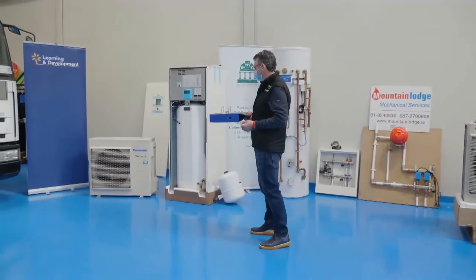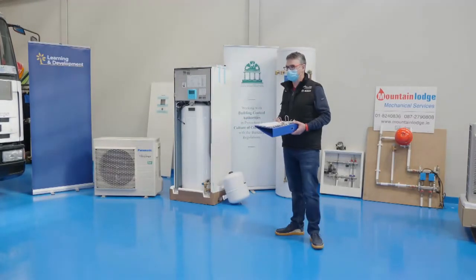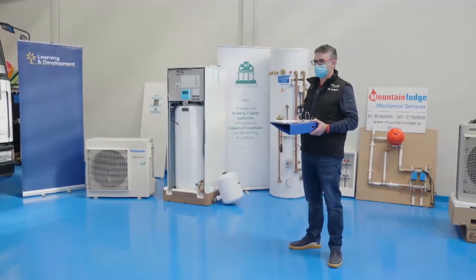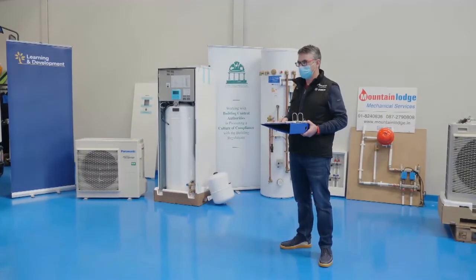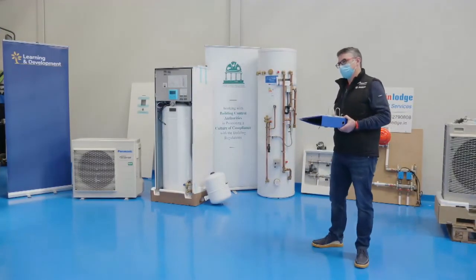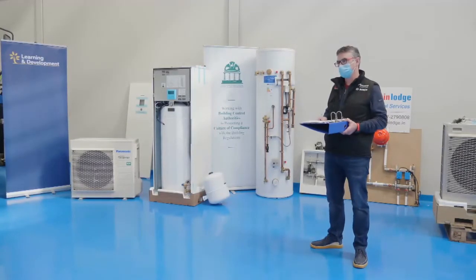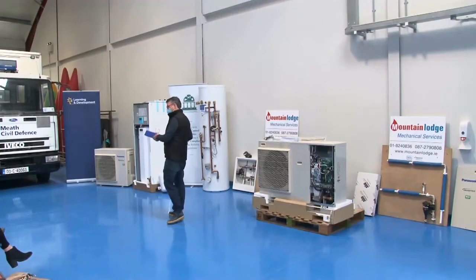You mentioned the SEAI HARP database. Any product, if you walk onto a site and you see a name that is not familiar, that you've never come across before, you can check with the SEAI. Every heat pump that's brought in has to be registered with them, with its efficiencies, on the HARP database. That would be the go-to for any product. Every manufacturer has to bring it in, get it approved, and get their efficiencies up there. So if the name isn't on the list, it probably shouldn't be in.